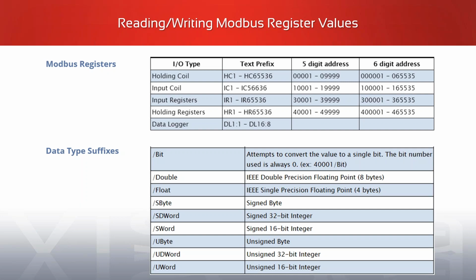No, there's a ton of new Modbus stuff going in. There's new devices that are out there all the time. One of the biggest changes that we've seen is a lot of devices that used to use a number of different protocols are now utilizing the Modbus standard to make their data available. For example, diesel generators. You'll see a lot of their ECUs that gather their data will now have Modbus as an option, whereas before they used to use some CAN bus standard or some other standard in order to communicate. So it's actually just as popular, if not much more popular than it used to be.